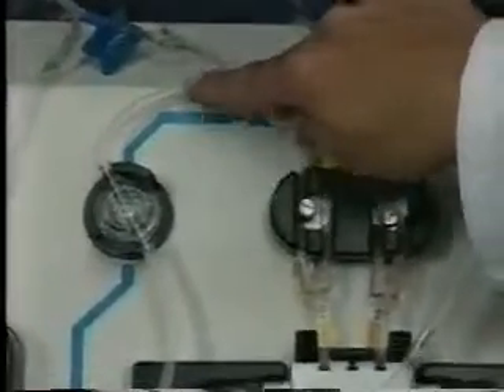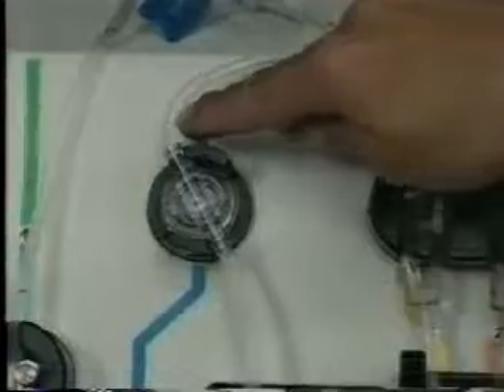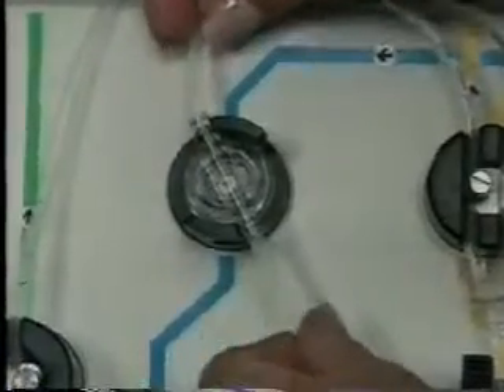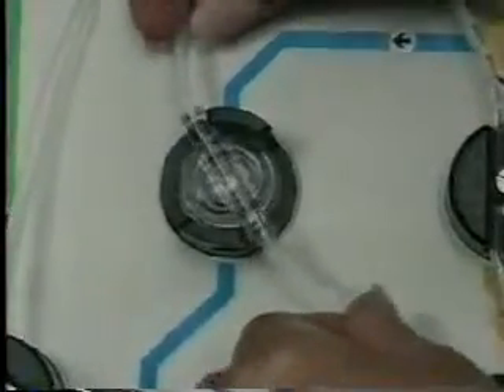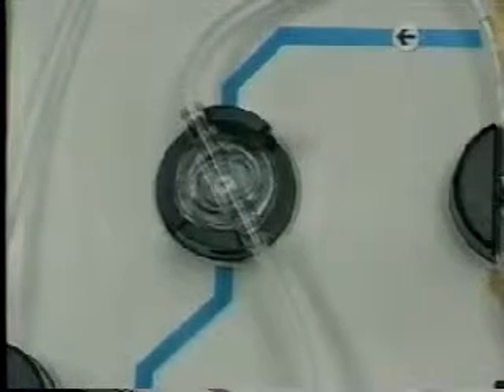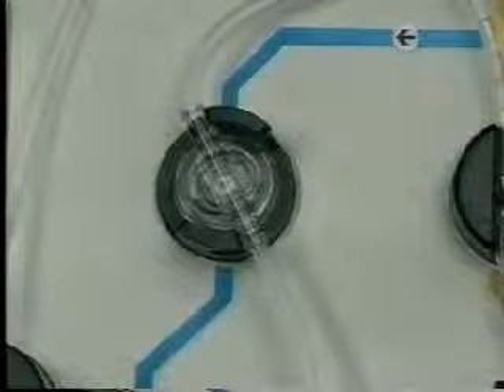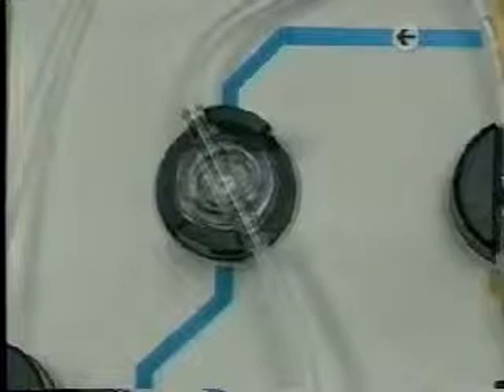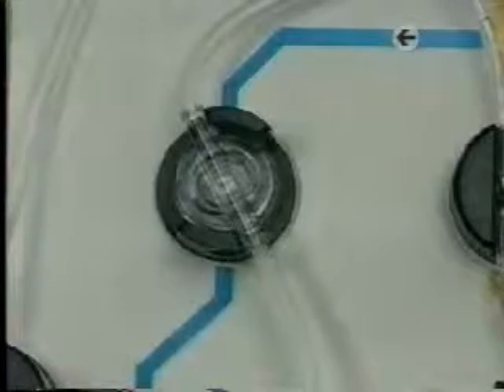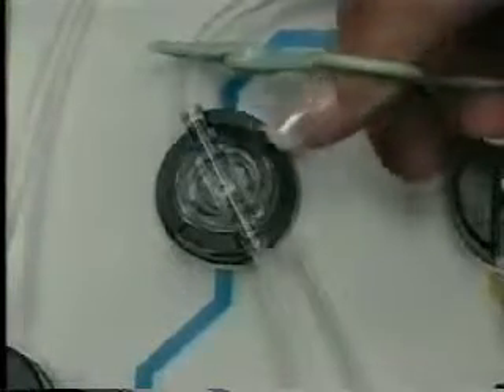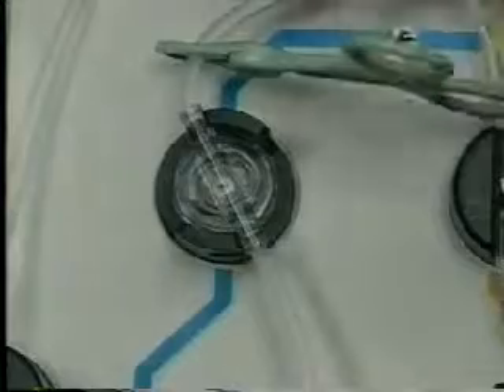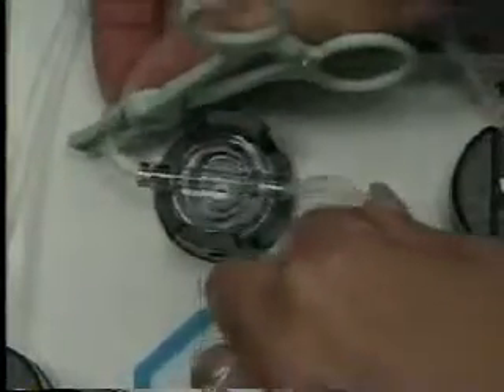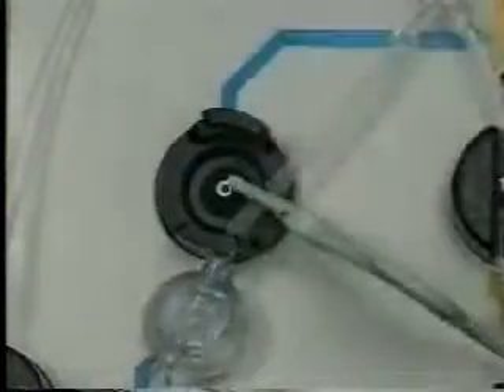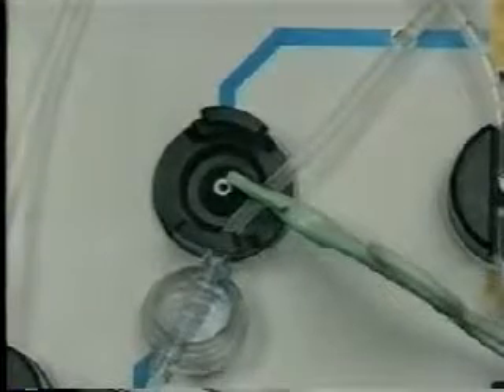If fluid is in the return line, you cannot simply remove the sensor and reseat it. Doing so causes the diaphragm to move out of position. We will now go through the steps to reposition the diaphragm. This procedure is covered in the Recovery Procedures section of your operator's manual. Clamp the line just above the return pressure sensor and remove the sensor from its housing. Then remove the tubing from the return line valve.